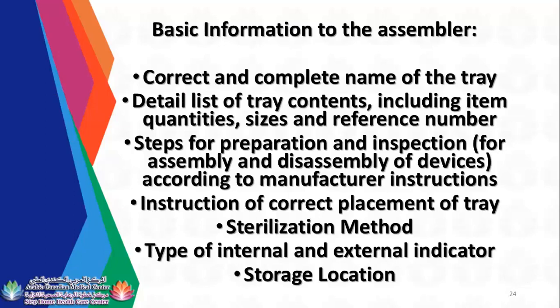Next, the list of tray contents, including item quantities, sizes, and reference numbers. There are times that you are allowed to put the instrument count sheets inside the tray. So it depends. You need to check, because especially if you are using steam sterilization, the ink might smudge and go onto the instruments. Sometimes the words on the paper will stick to the instruments. So you need to check if it is allowed or not. Sometimes they use a different ink so that the count sheets can be placed inside the rigid container.